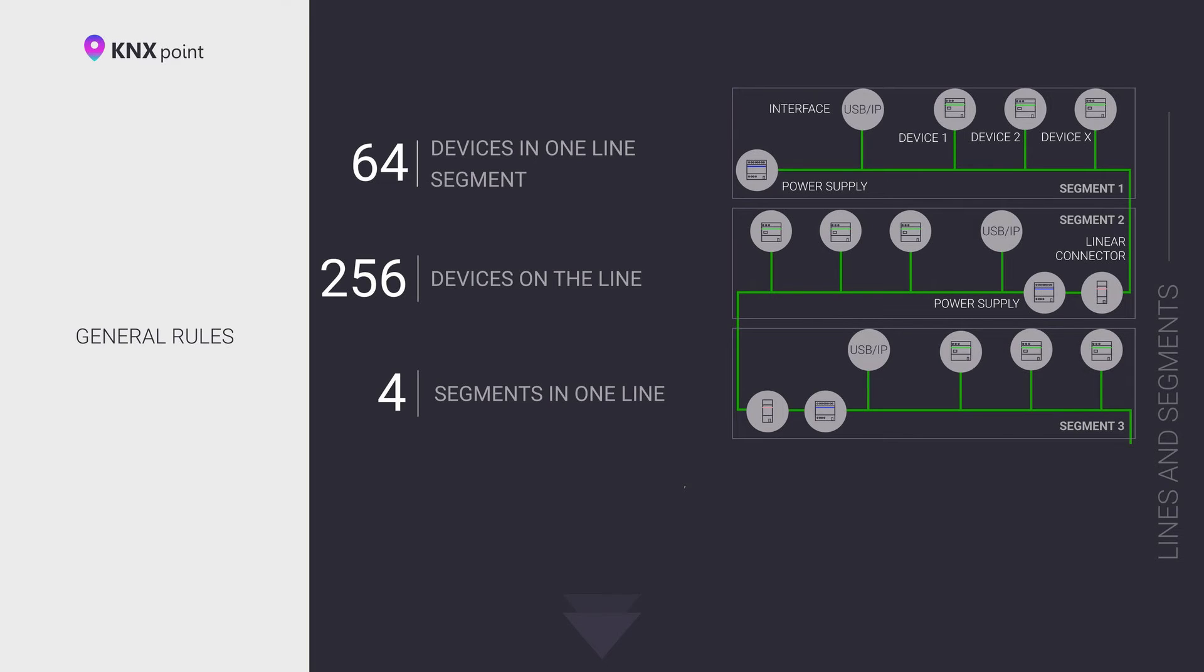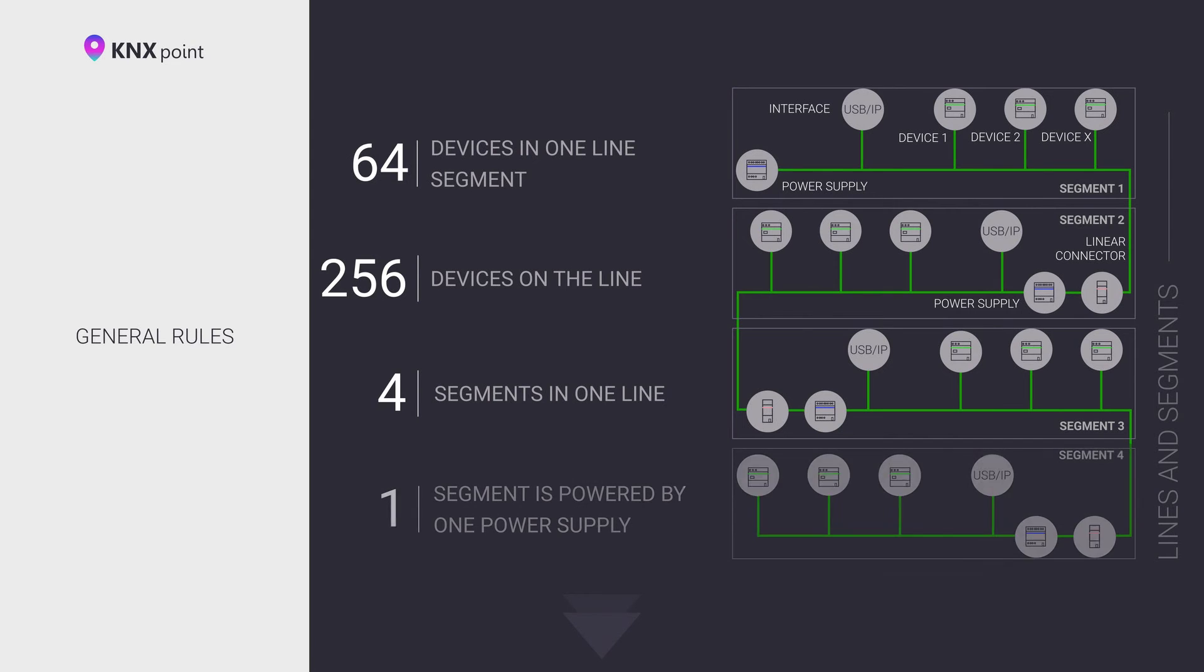Each bus segment must be connected to other bus segments or a group of segments with a line coupler. KNX devices for the wired line, manufactured before the end of 2018, belonged to the TP64 technology. This means that no more than 64 devices could be connected to one line segment. To connect all 256 devices to one line, it was necessary to divide the line into four segments using line couplers.